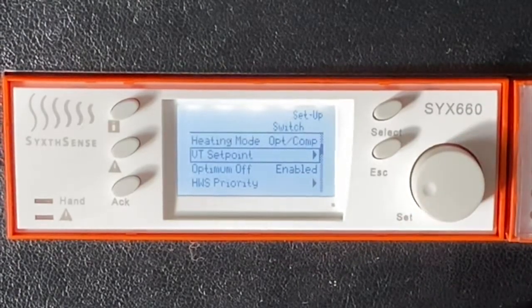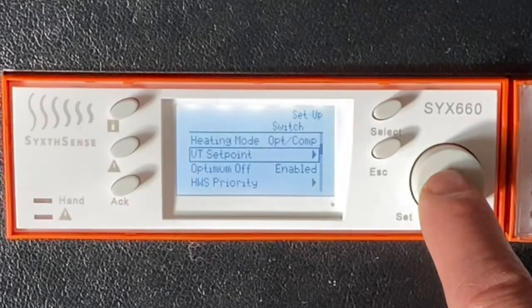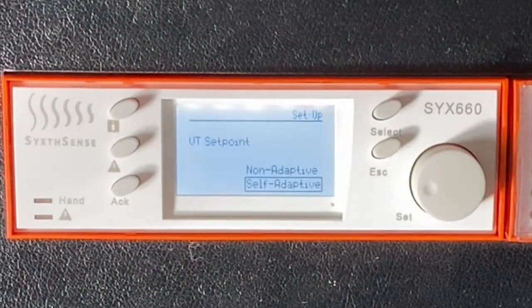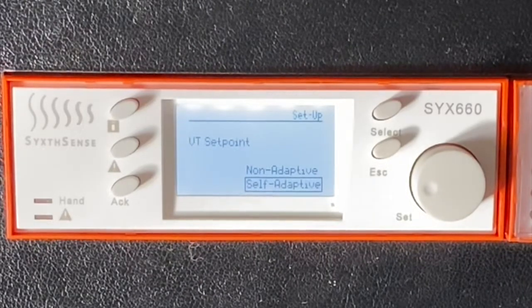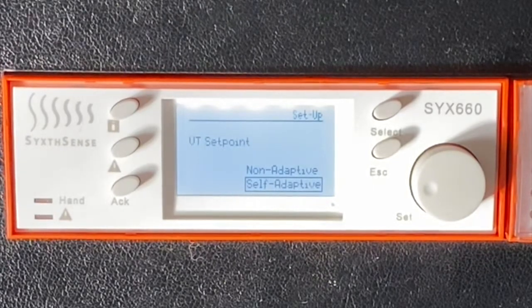What we also then have next is VT set point, and we can choose whether it's adaptive or non-adaptive, or self-adaptive. This is basically room influence. So this is where we look at the room sensor, we look to see if it's above or below the current room set point, and we have an effect on the calculated flow temperature based upon a ratio.